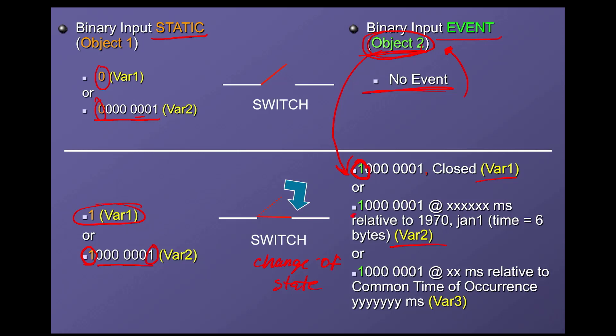Object 2 variation 2 says we have an event recorded at a specific time. DNP3 uses six bytes counting milliseconds from January 1st, 1970 — that's 48 bits of milliseconds. So it's essentially a synchronized time starting January 1st, 1970 and counting up in milliseconds. When it comes to variation 3, this is something called CTO — common time of occurrence. CTO is a time that can be sent out over the network as a broadcast message to essentially synchronize all the clocks within your network, so all RTUs are synchronized to that same CTO time.